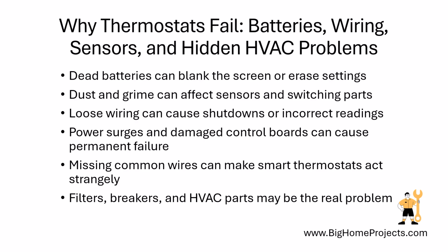Smart thermostats may fail when their internet connection is lost, but losing the connection usually does not mean the thermostat itself is broken. Some smart models also need a continuous power wire, often called a common wire, and may act strangely if that wire is missing or incorrectly connected. Before replacing the thermostat, turn off power to the system, install fresh batteries if it uses them, gently clean the outside, and check whether the heating or cooling equipment works from its own controls.